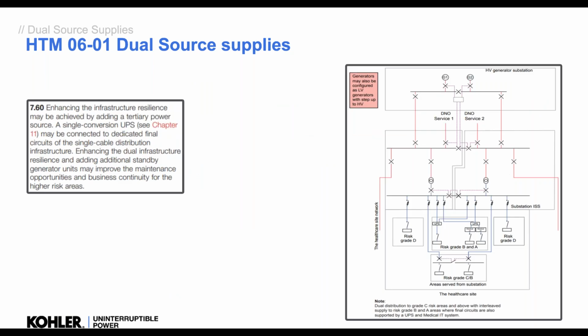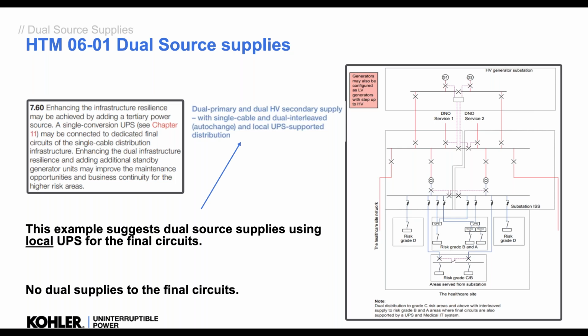So what many people look at is these drawings in HTM, these diagrams and examples. It talks about single conversion UPSs for final circuits. People look at this drawing and we see the UPS here and here feeding the final circuits, in this case the medical IT, the IPS. And they see the UPS is fed from two different sources. But that's because the medical IT needs two sources, not necessarily the UPS. The final circuit needs two sources. So this is a final circuit UPS with dual source supply for those final circuits.